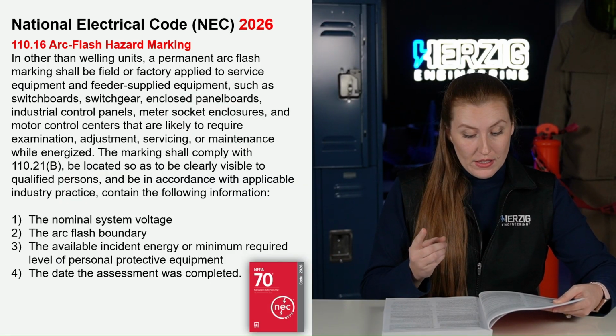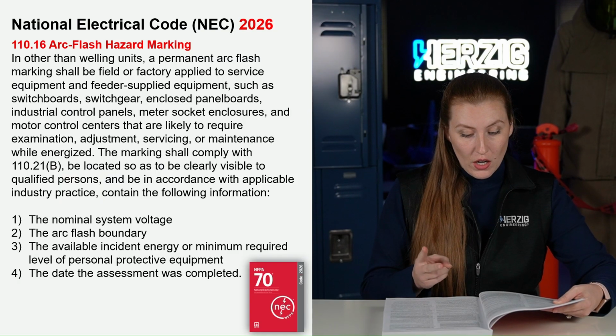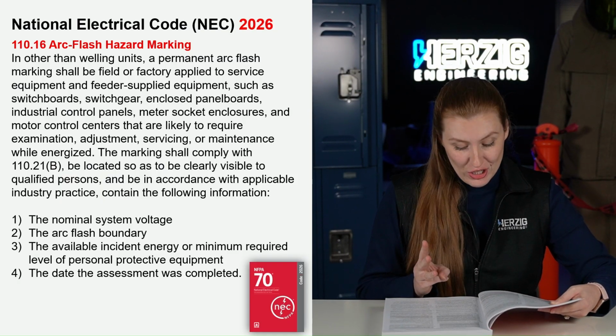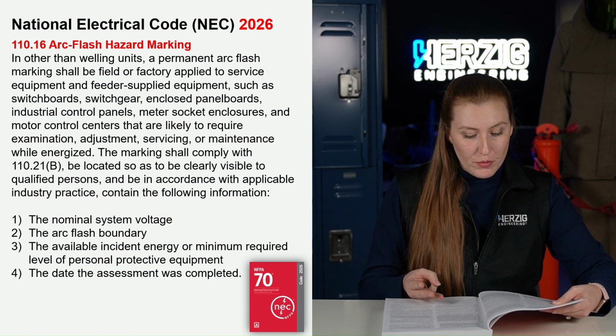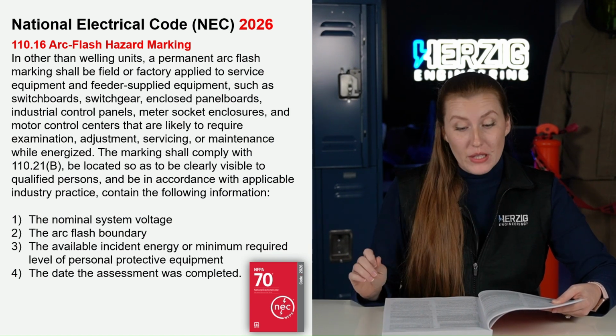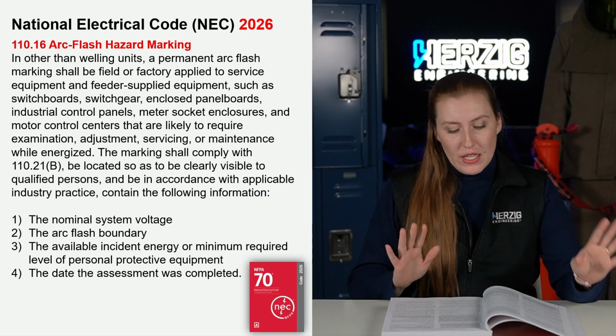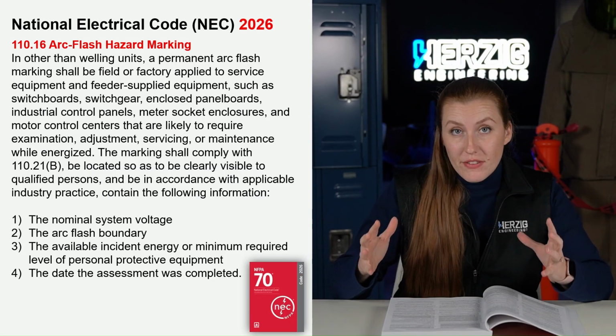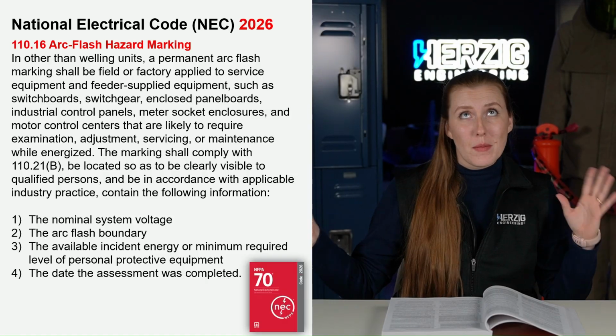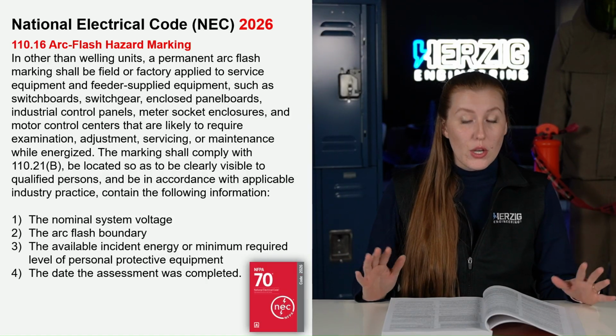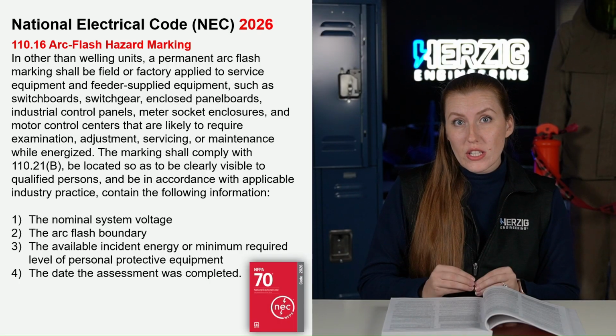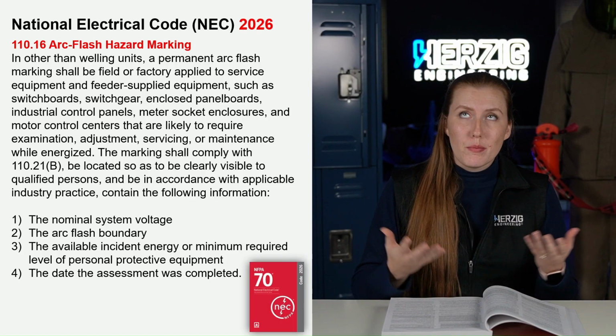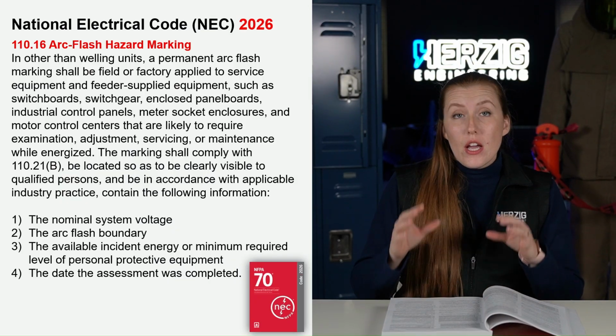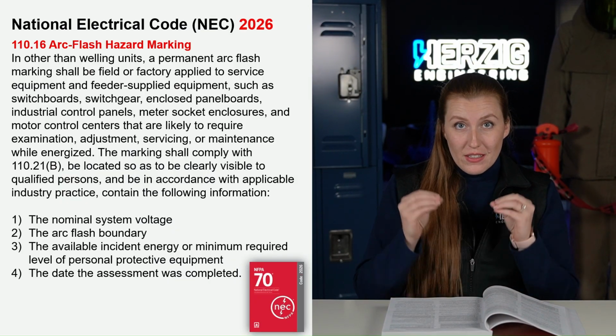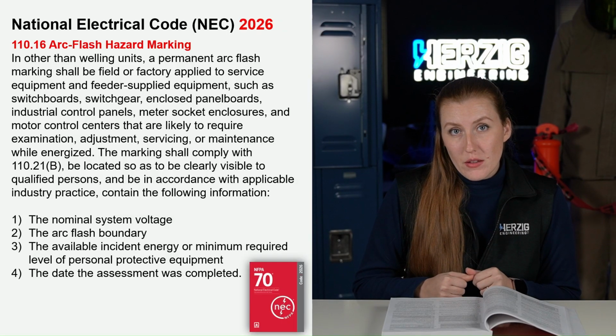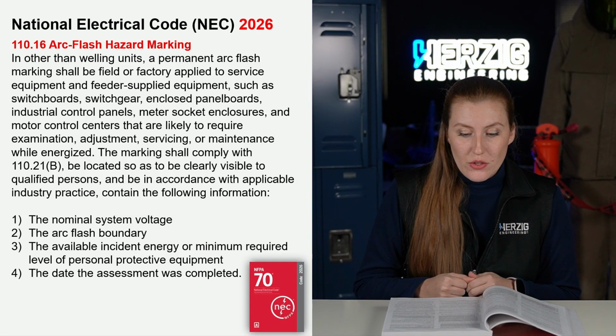So the first thing they point out is that it has to have the nominal system voltage, the arc flash boundary, the available incident energy or minimum required level of personal protective equipment, and the date the assessment was completed. So not just the date that it was applied, but the date that the assessment was completed. It has to have specific arc flash information, so no generic warning, like there might be some hazards here, follow best practices. No, it has to have that calculated incident energy level or the minimum required PPE that's based on the hazard level that you're facing. No generic information, specific, detailed.